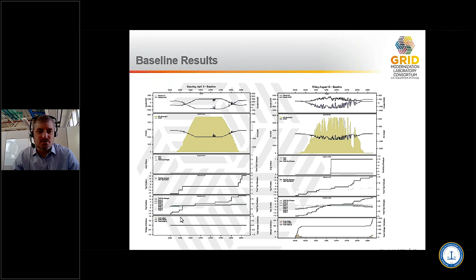So this is the base case. Suffice it to say the system is not behaving the way we would love. If we go to autonomous local control, meaning the PV inverter is doing, say, a constant power factor operation without much major control, we actually get some benefit. You now see some reduction in the number of capacitor bank operations and tap voltage regulator settings, especially during the nice sunny day. On the cloudy day, though, it doesn't help much. Things are still moving around too much, and we don't get much benefit even from that local autonomous control. Let's go to the next slide, please.